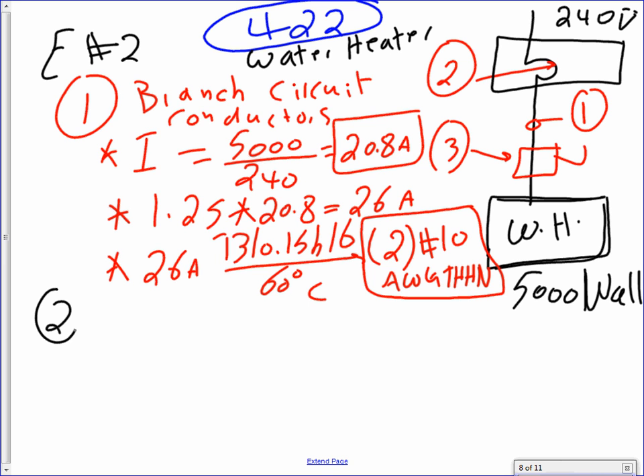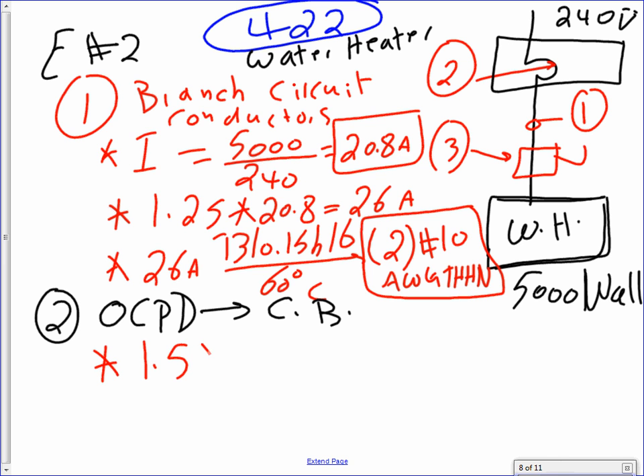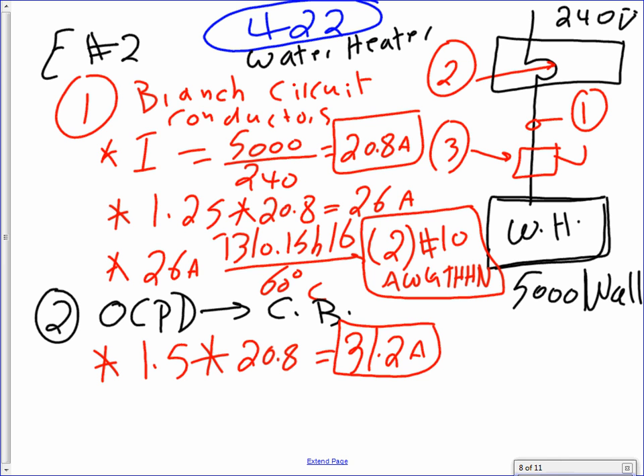Number 2 is the overcurrent protection device, which is the circuit breaker. For the circuit breaker, guys, you take 1.5. Remember that table that we were just looking at, 150%, multiplied by 20.8. If you take 150% multiplied by 20.8, that will get you 31.2 amps.